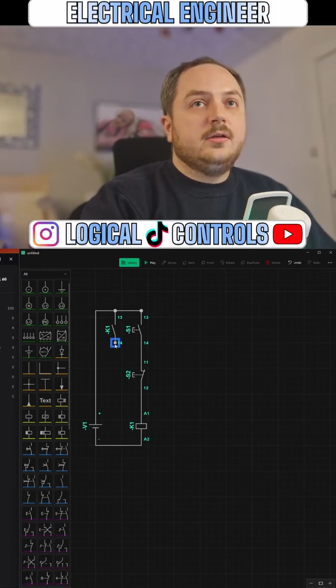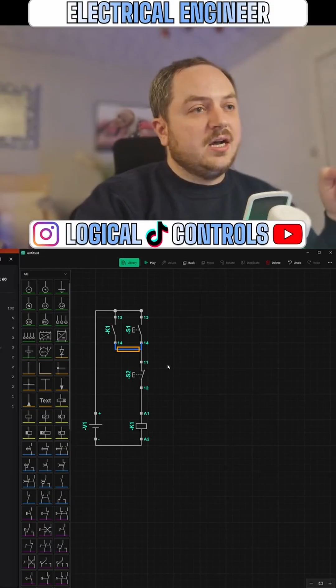To make it a latching, or sealing as you called it, or holding as some people call it, you need a contact of the relay you're controlling to go in parallel with the start button. At the minute I pressed the start button it came on, and when I let go it went off. So you put a contact in parallel to the start button, and I just dab it, click it once. I push my finger on the button once, and the relay energizes and holds itself in. So that's where the latching or sealing comes from.